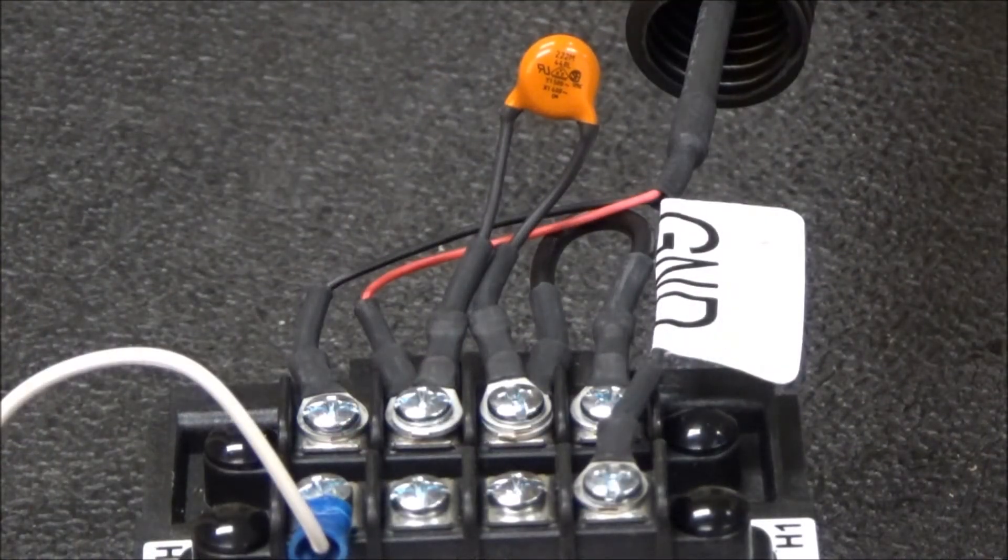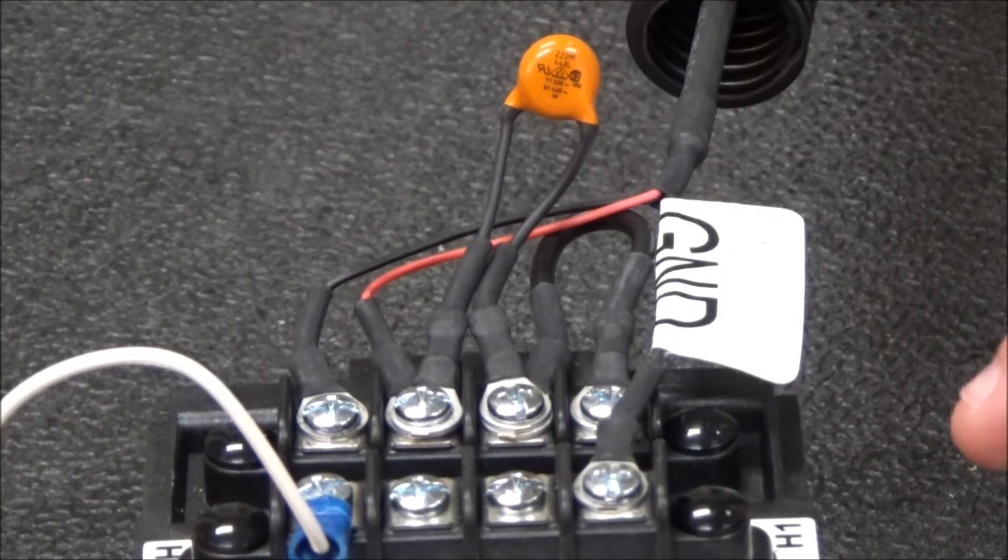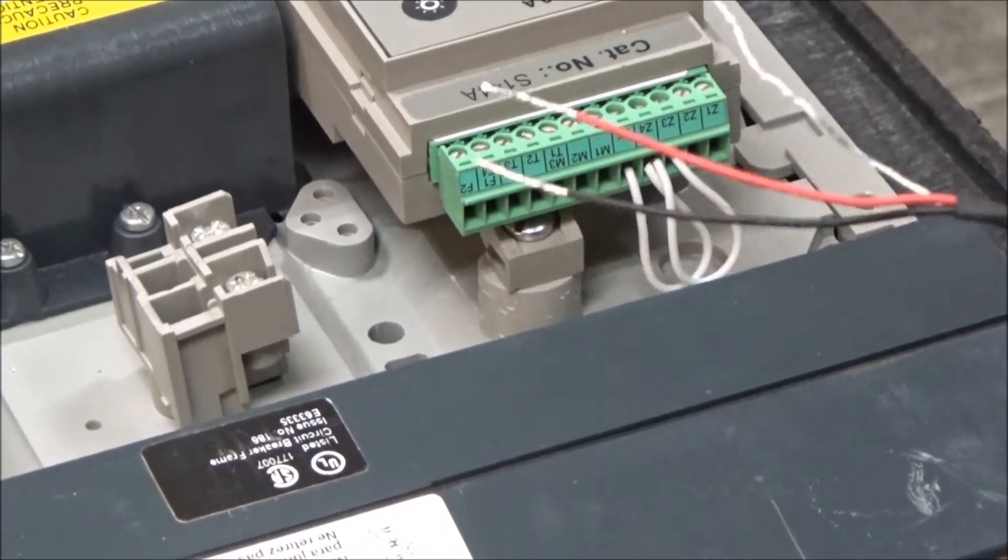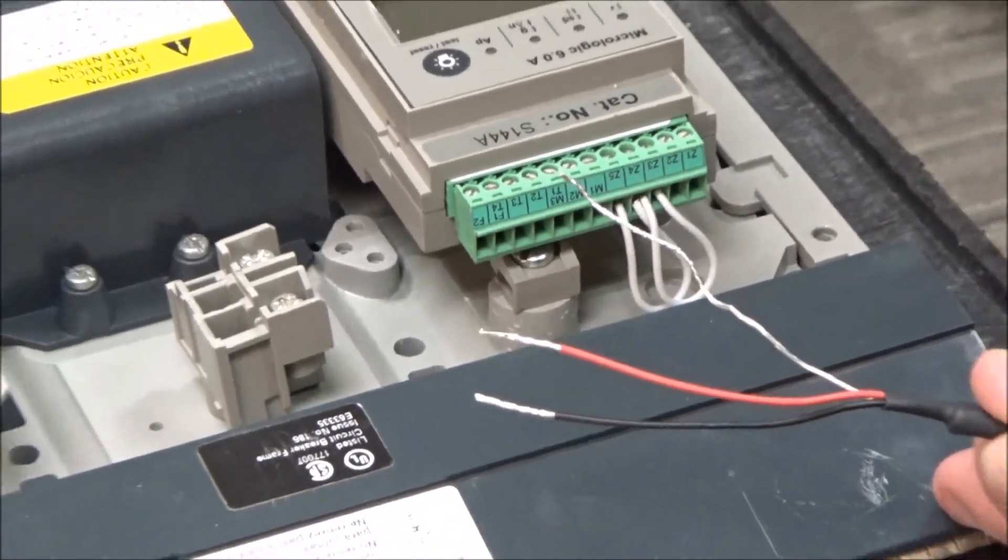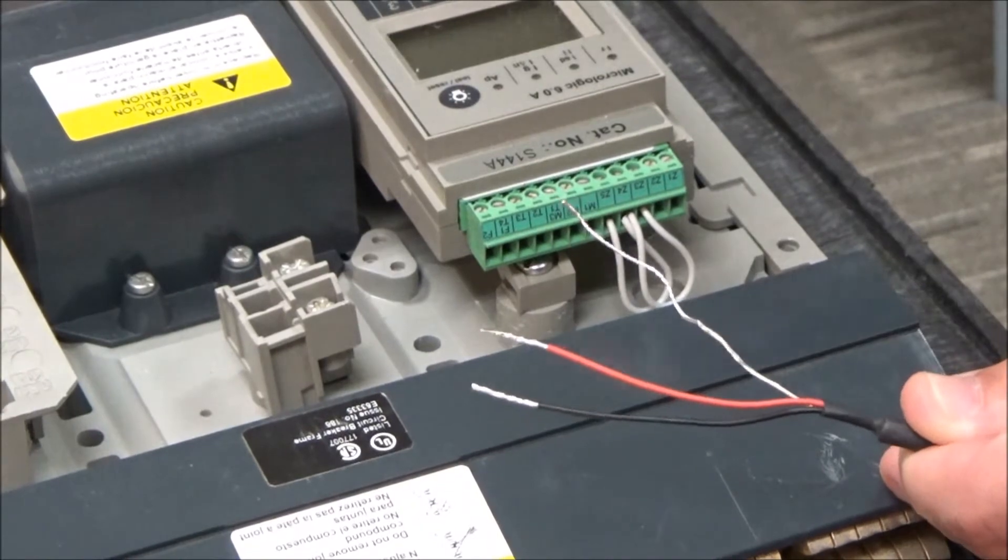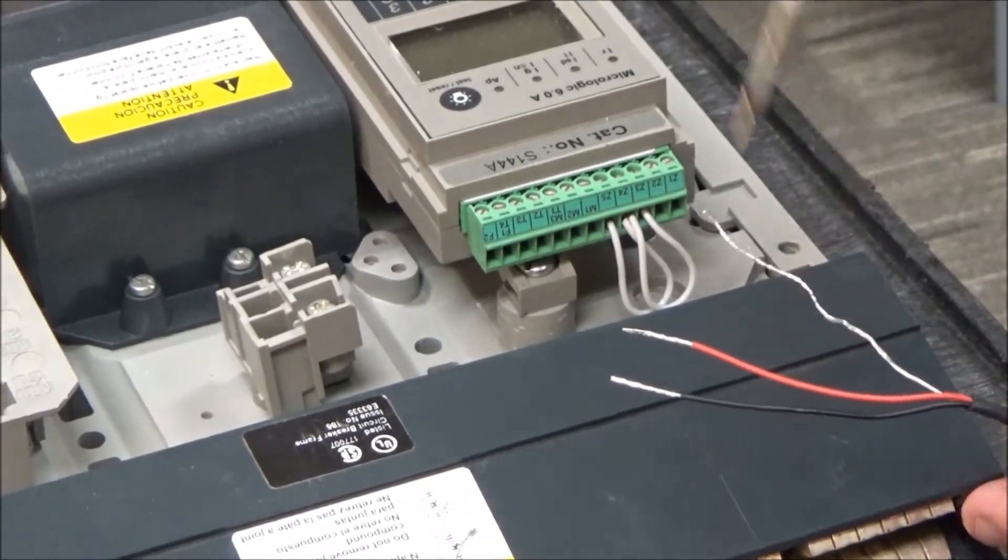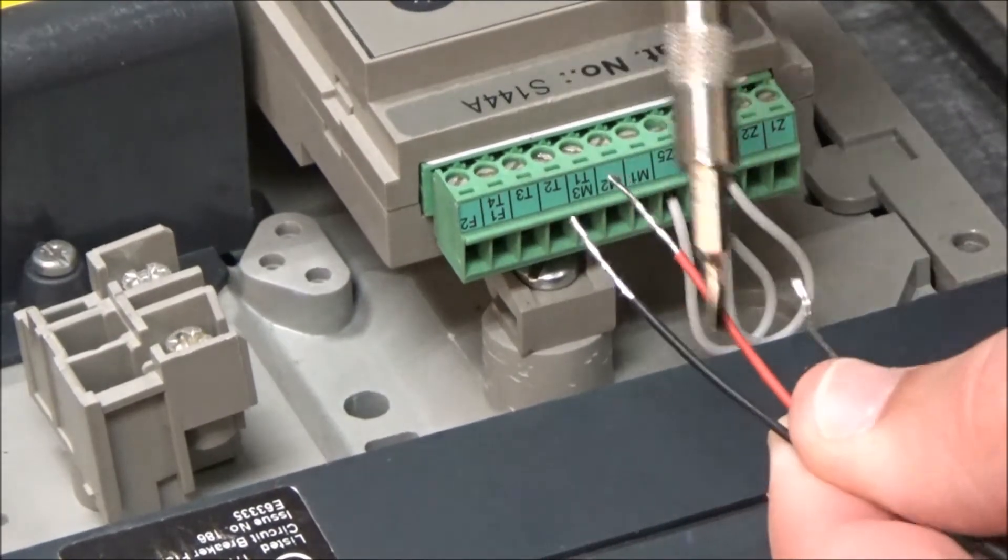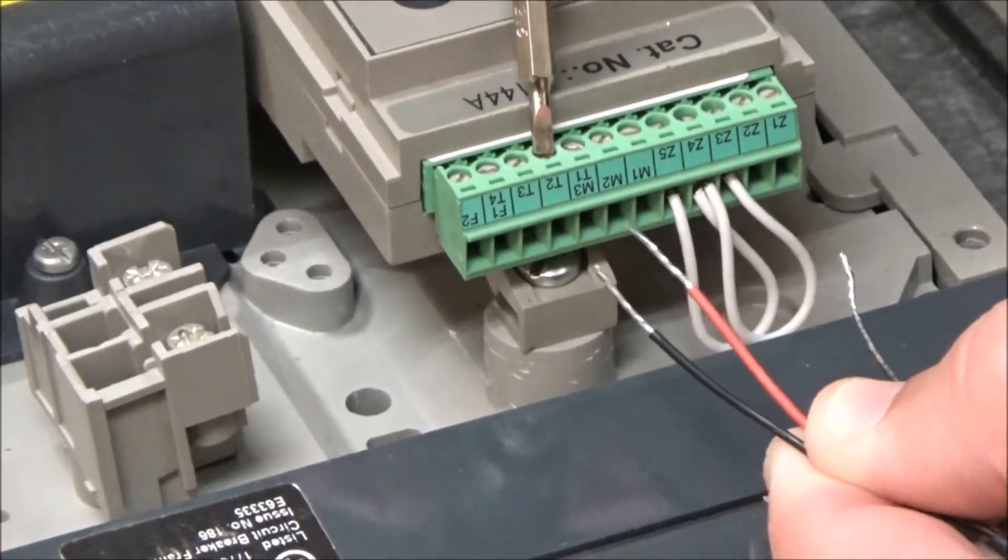Once you have all the necessary connections made on the Neutral CT, you will then attach the other side of the NCT wiring kit to the trip unit. The red wire will go on the T1 terminal, the black wire will go on the T2 terminal, and the bare wire to the T4 terminal.